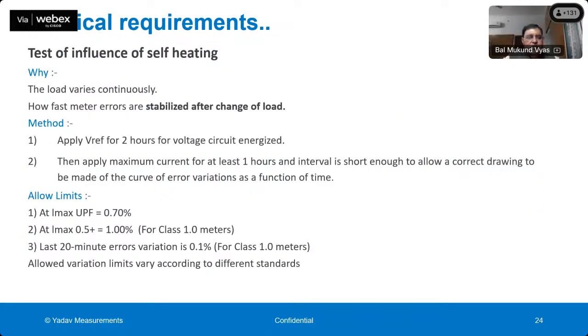Another important electrical requirement is the test of influence of self-heating, because the meter has an electronic circuit and the current is passing through the meter, so there is heating in the meter. This heating should not cause changes in the accuracy of the meter and should not damage it. So there are limits specified for the change in error because of self-heating.